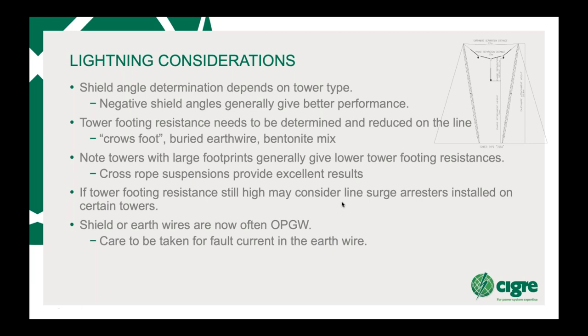Then the shield or earth wires are now often OPGW, so you need to look at the fault current in the particular earth wire, and whether you need, in fact, to have a different kind of earth wire to take current away from the OPGW. So that's also something to consider.